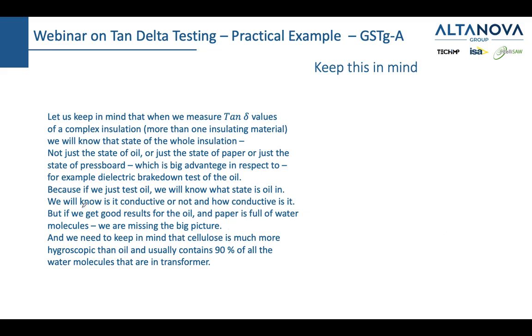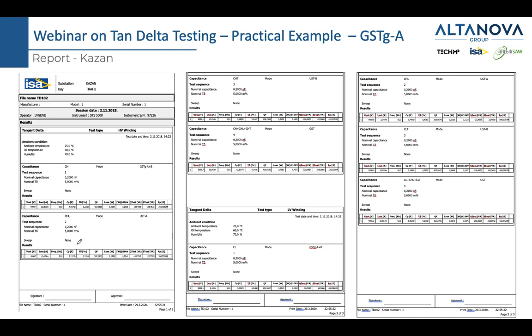Because if we just test the oil, as I said, we will know the state of the oil, we will know if it's conductive or not and how conductive it is. But if we get good results for the oil and the paper is full of water, then we're missing the big picture. And as we mentioned before, most of the water, even up to 95 or even 99%, stays in the hygroscopic paper and the press board. So we have now one example and actually four more slides and then we're done.